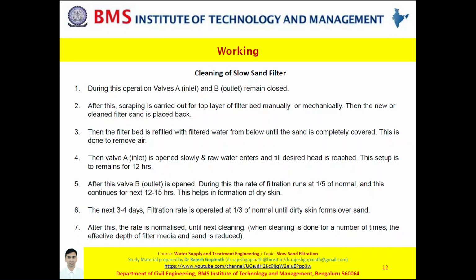After this is done, a new layer of filter bed, that is, a new layer has to be placed over your filter media. Once this is done, you need to slowly open valve A again. So what happens is the raw water once again enters from sedimentation, enters the inlet chamber, rises, falls into the filter bed gradually, and then it starts filling up the entire chamber.